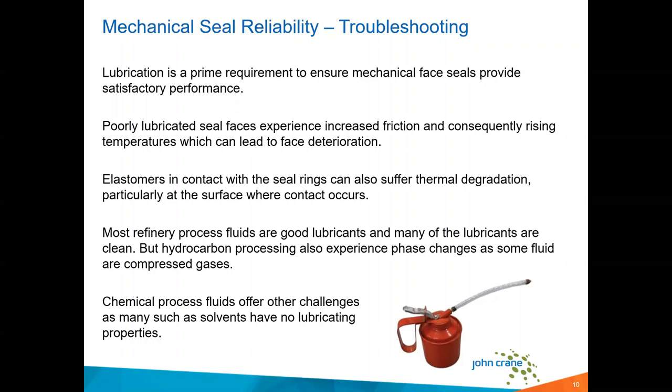The majority of mechanical seals are going to use good liquid lubrication between the seal faces in order to provide satisfactory performance. Any instance where you have poorly lubricated seal faces is going to result in increased friction, increased temperatures, and ultimately deterioration of the seal faces. Subsequently, your secondary elements, such as the elastomers in contact with the seal rings, can suffer thermal degradation with those localized conditions, and particularly where the surface contact occurs, any additional heat generated by face friction is going to get transferred right to the elastomer.